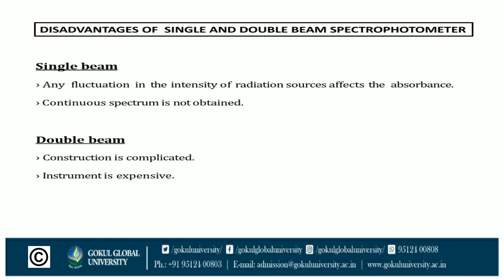Now the disadvantages of single and double beam spectrophotometers. The single beam disadvantage is that any fluctuation in the intensity of the radiation source affects the absorbance. A second disadvantage is that a continuous spectrum is not obtained.